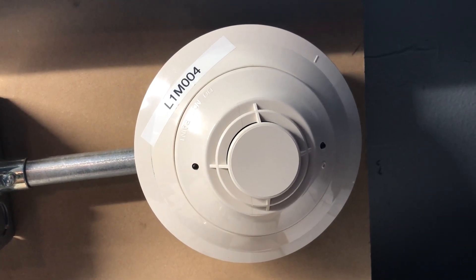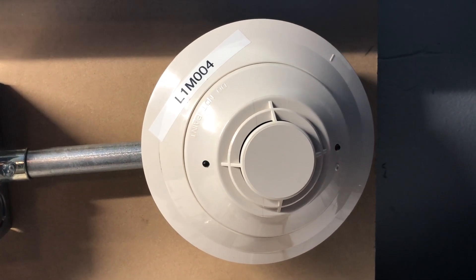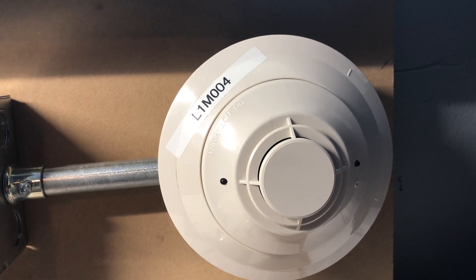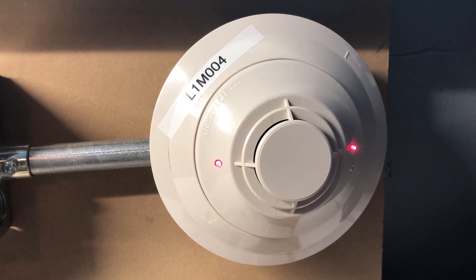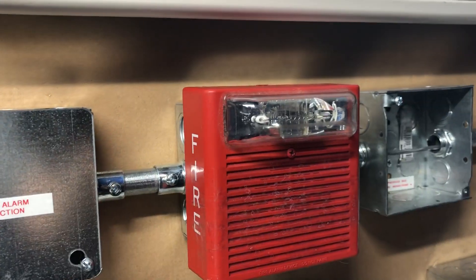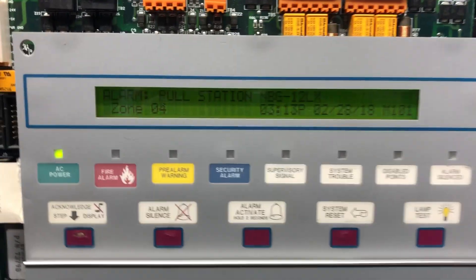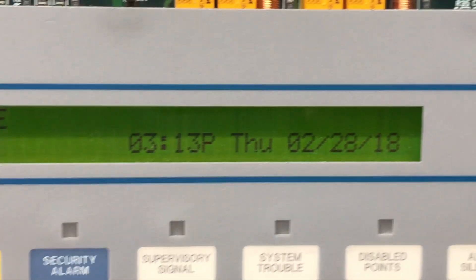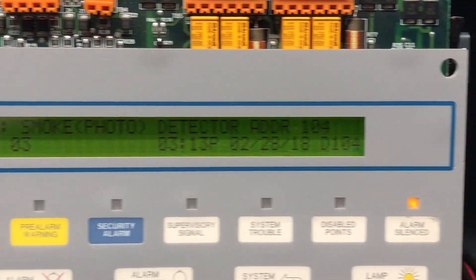This is smoke detector spray. Let's just spray it. There we go. And there you have it — shows a fire alarm, we've got the fire alarm blinking, and it smells like smoke detector spray in here.